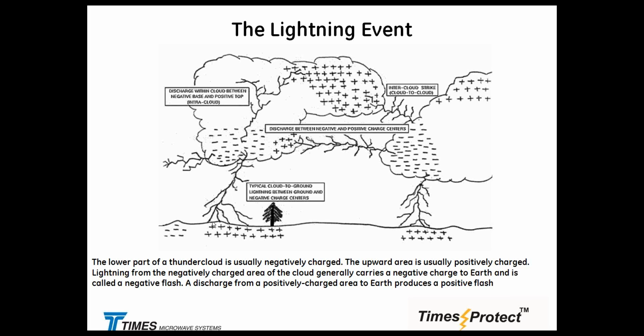And at a given point in time, even though we don't have a free current flow to return itself from the source, we're going to be seeing a rise in step potential on the ground. So we might not even have a current flow, but the ground can go to 100 kV, 50 kV, and you are going to see small streamers blowing on the top of the tower, on trees, on high-rise buildings, and so on. So that opposing streamer is already an indication where the step potential rise will be taking place. And as I say, if you smell ozone, it's usually too late to run. So anyway, sit low at this point.